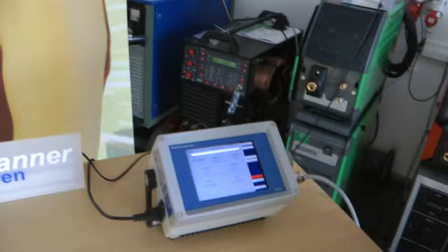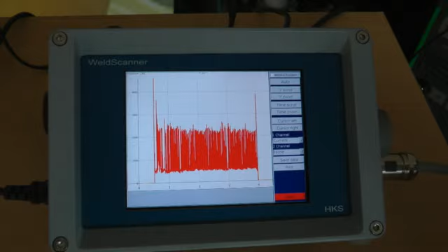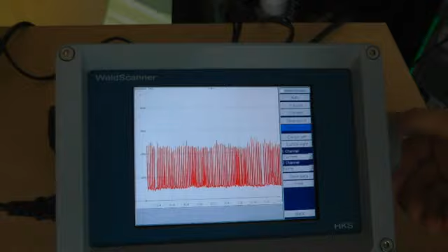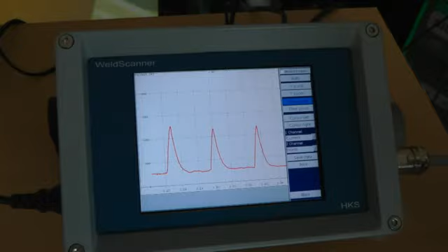Number one is the so-called scope mode. That means we sample the data not with 100 measuring points per second like in the normal logger mode, but in scope mode we store data with 6400 measuring points per second. That means if you have, for example, a short circuit process, you can see the short circuits, zoom through the data, and time-scroll through it. You have all possibilities for evaluating the welding process. So every time a technician cries for an oscilloscope, a digital storage oscilloscope, he can instead easily use the weld scanner for all the welding parameters.